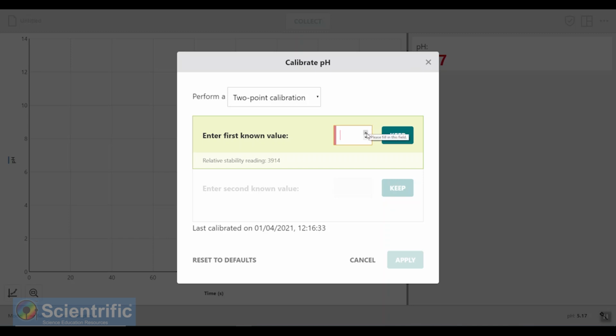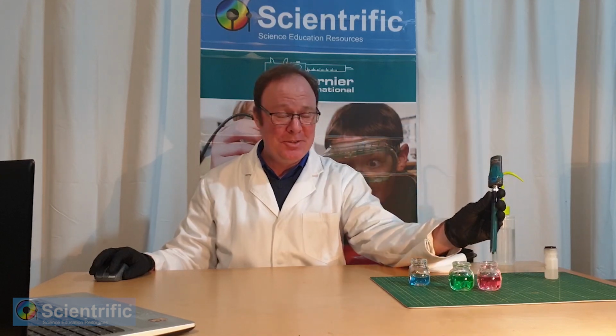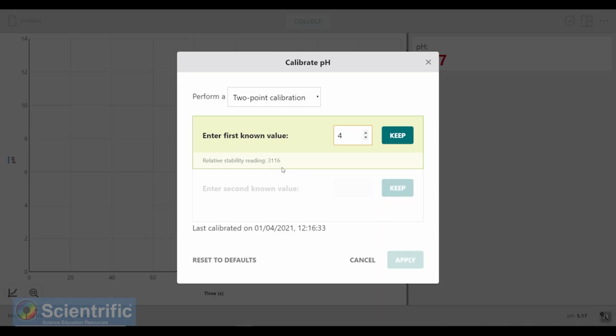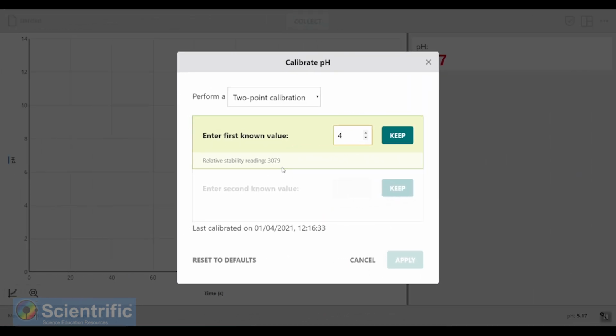At this stage, I want to put in my first known value. In this case, it is going to be the buffer 4. So I take this probe and I put it in my number 4 buffer solution. Over here on the screen, you can see I have this relative stability reading. I want to wait until this number stops changing. This may take up to 30 seconds. Now the number is quite stable, I'm going to go up and I'm going to keep that.